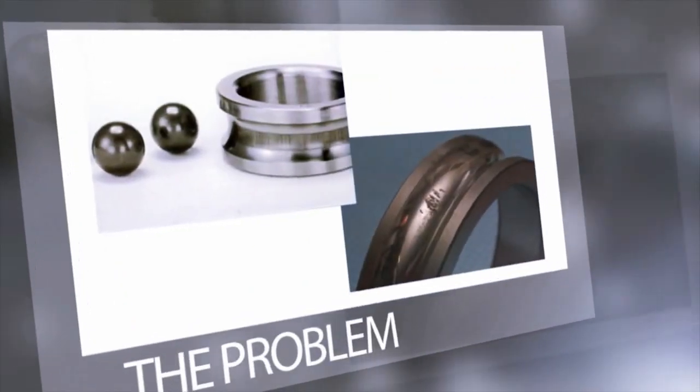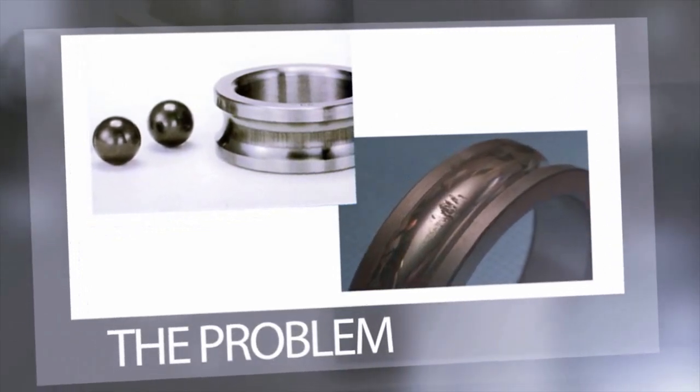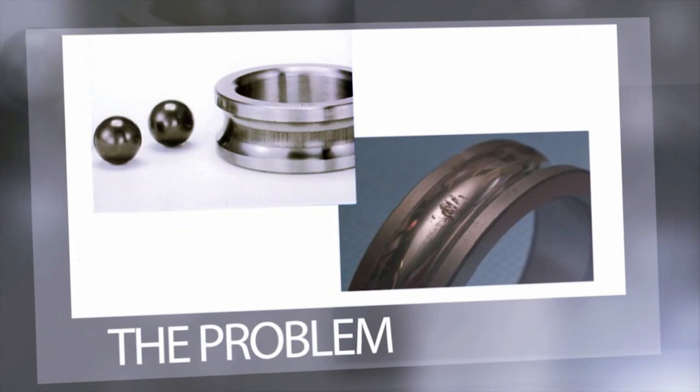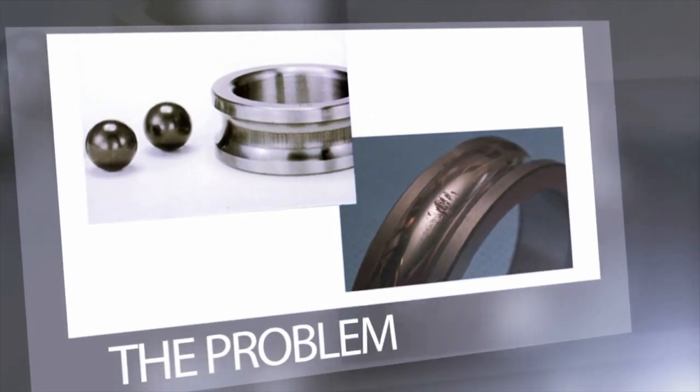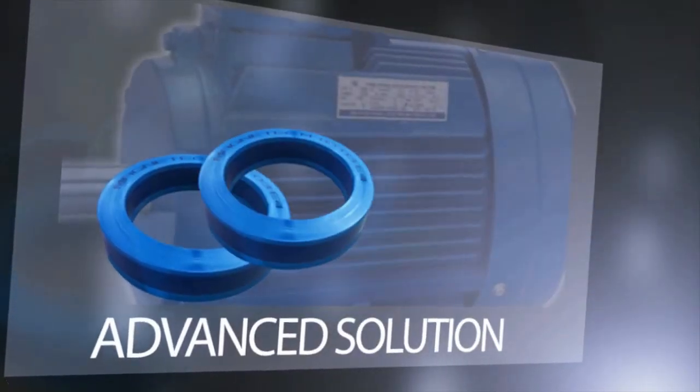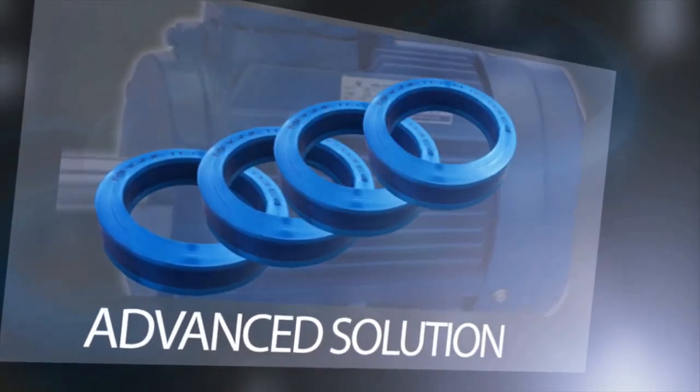A problem concerning all electric motors with VFDs, also known as inverter output, is the bearing damage and circulating currents caused by high-frequency currents the VFDs produce, resulting in pitting, fluting, frosting of bearings, lubrication breakdown, and destruction of the bearing. This can now be virtually eliminated. We are proud to present the most technologically advanced solution to suppress circulating currents.